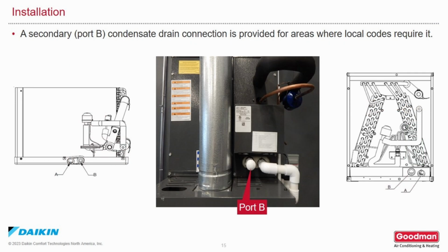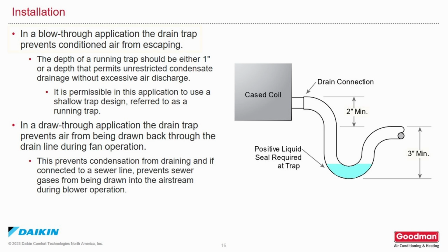A secondary condensate drain port B is provided for areas where local code requires it. In a blow-through coil application, the drain trap prevents conditioned air from escaping through the condensate drain. The depth of a running trap should be around 1 inch, or a depth that permits unrestricted condensate drainage without excessive air discharge. It is permissible in this application to use a shallow trap design, referred to as a running trap.